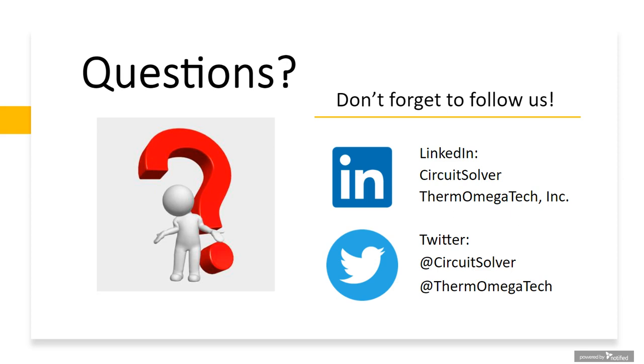Now, that being said, there may be some older systems out there that may have limitations and may not have the expandability. So that's a good question from that standpoint. If you're trying to do a retrofit into a building that has a system, you do need to make sure how expandable the I/O is if there's not enough spare I/O already existing.